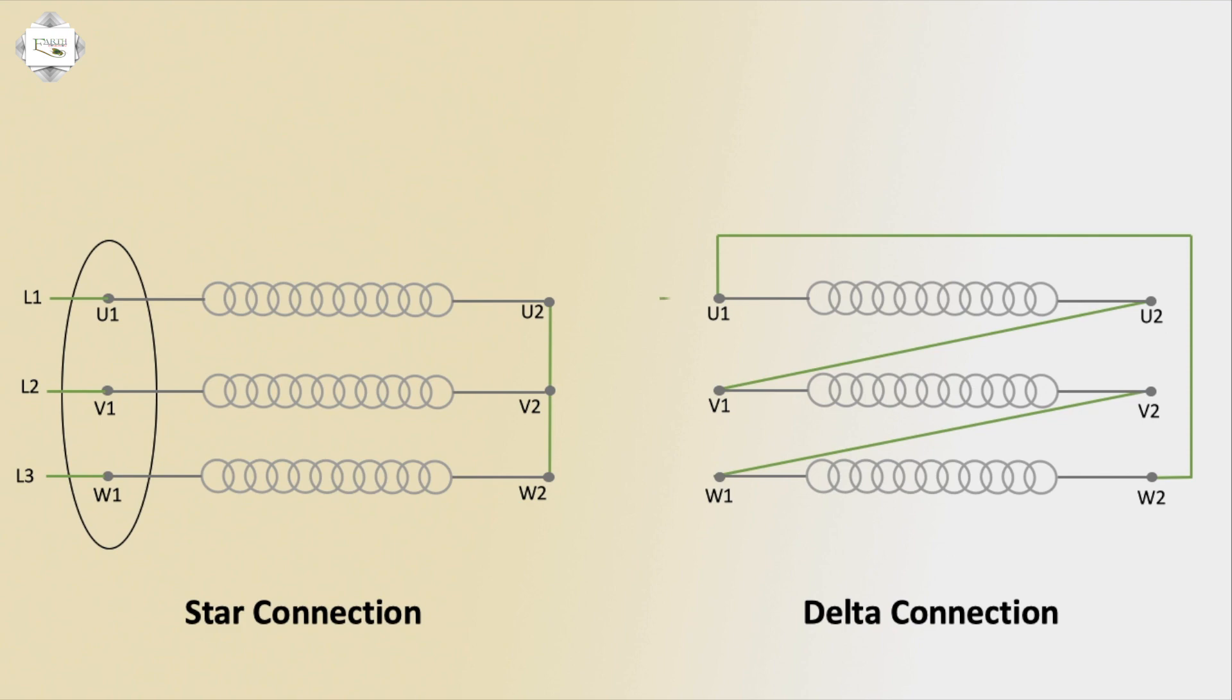For the 3-phase motor delta connection: L1 connects to U1 and W2, forming the first phase connection. L2 means second phase yellow, which connects to V1 and U2 for the second phase connection.